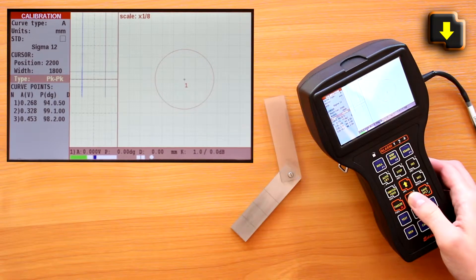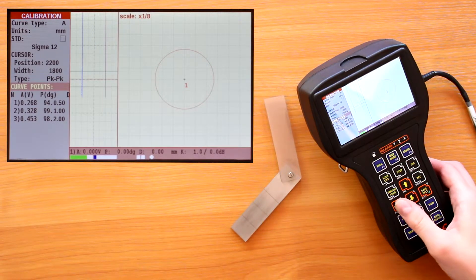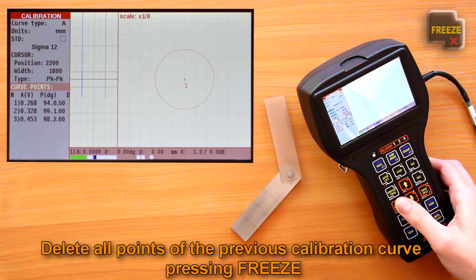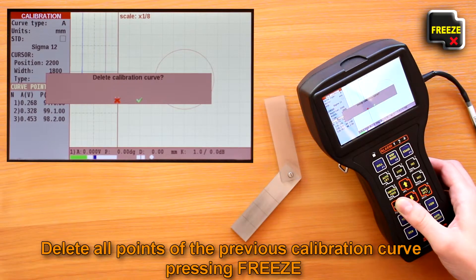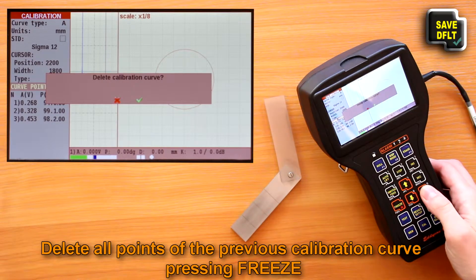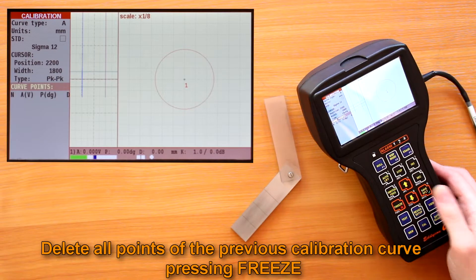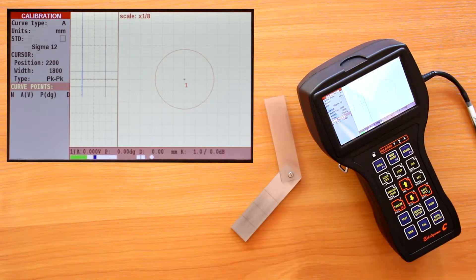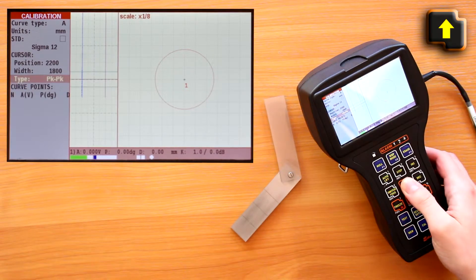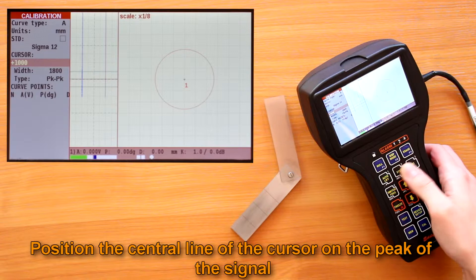Before plotting the calibration curve, it is necessary to move to the curve points item and delete all points of the previous calibration curve by pressing the freeze button. Move to the position item and position the central line of the cursor on the peak of the signal from the minimal defect.